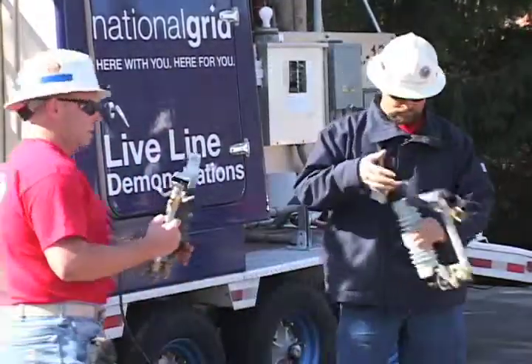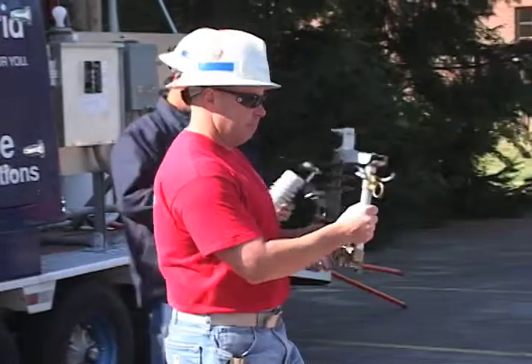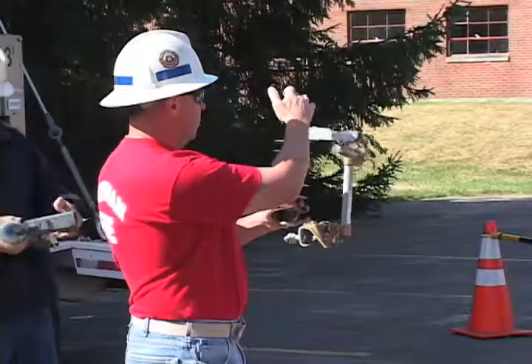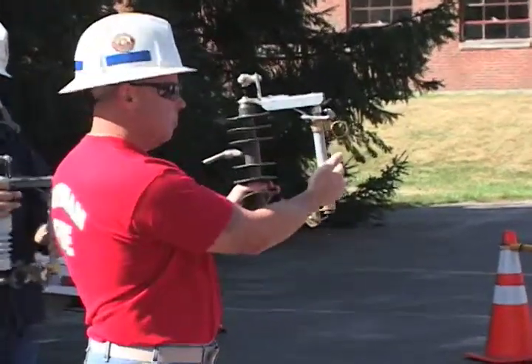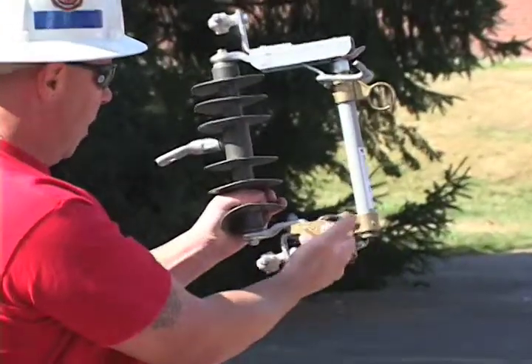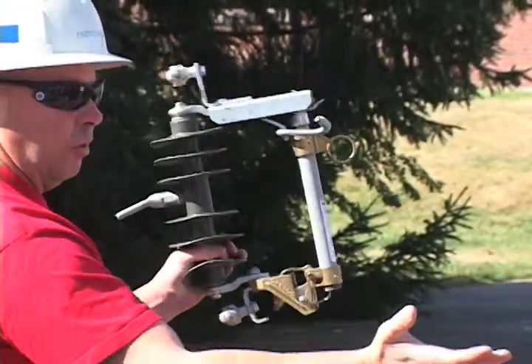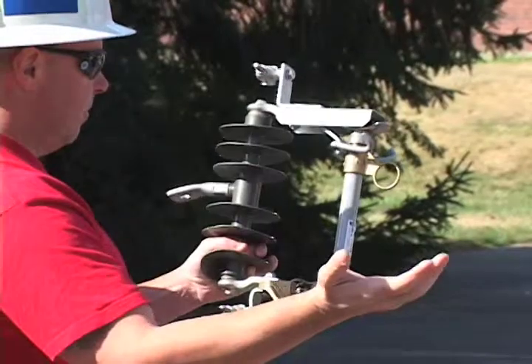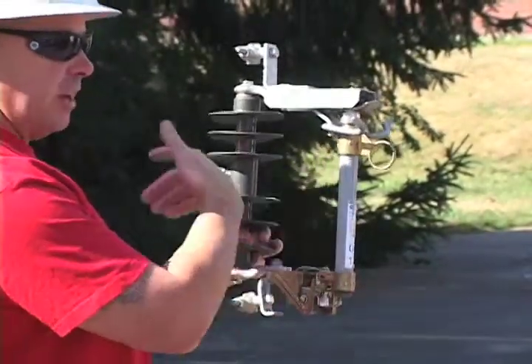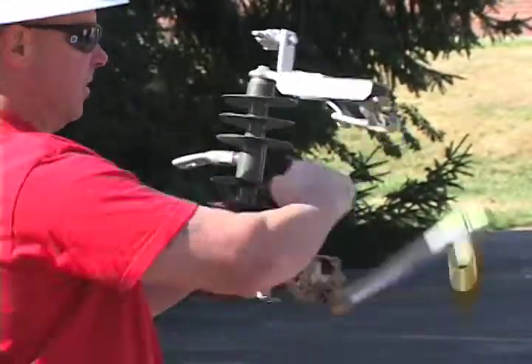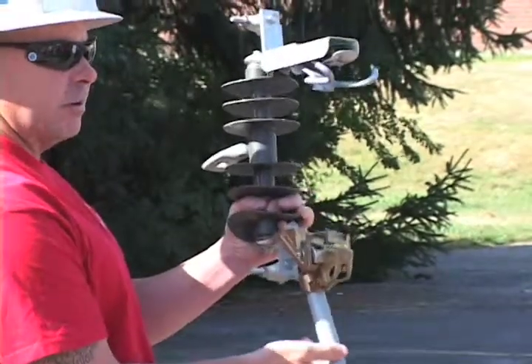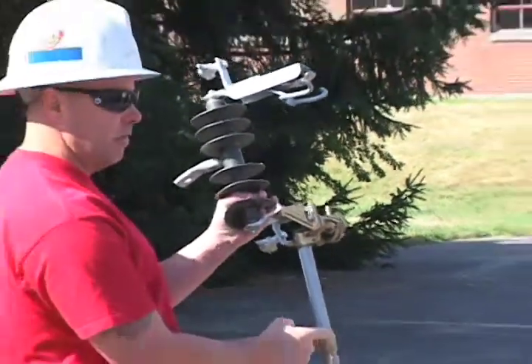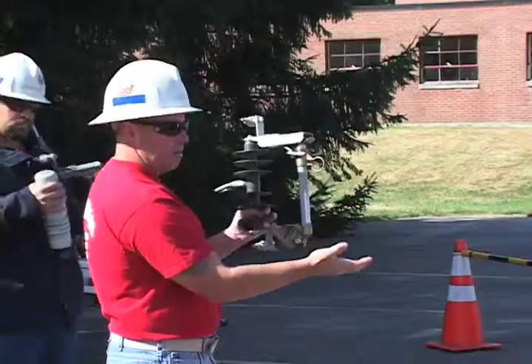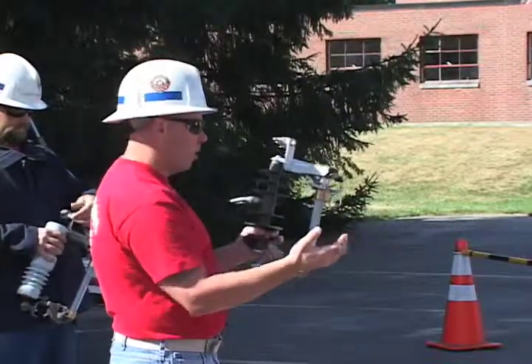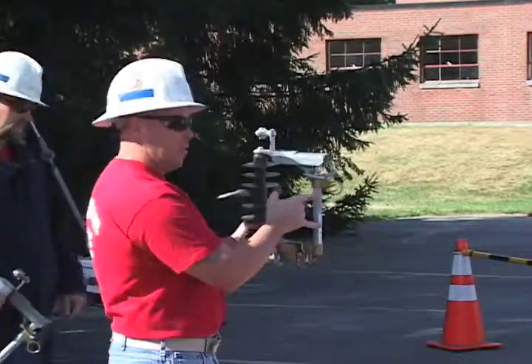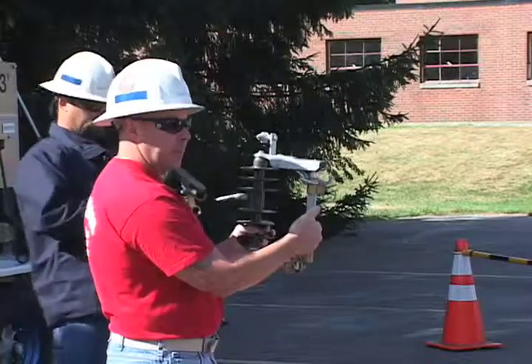This is what we call a cutout. Electricity comes in the top, through this fuse holder, out the bottom to the line. When a fault is created, the fuse blows and this falls down. Sometimes they get full of garbage and won't fall down, so you get that call about a fire on the pole, and it's the garbage in there burning.